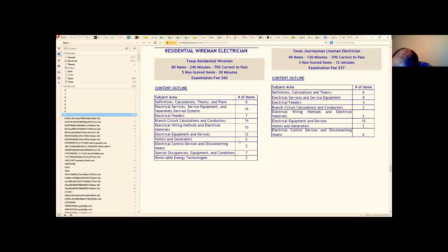GFCI protected. Yeah, they've got to be residential branch only. They have to have GFCI, and they can't be more than 20 amps. So maximum 20 amps. And you just put a note right above the top. Just put must have all 3.